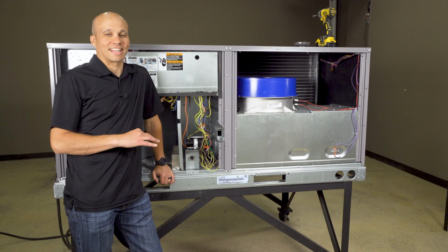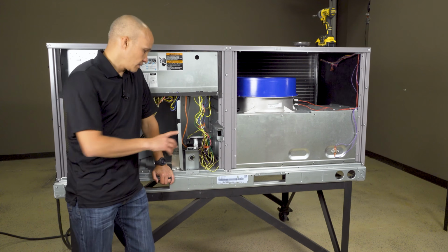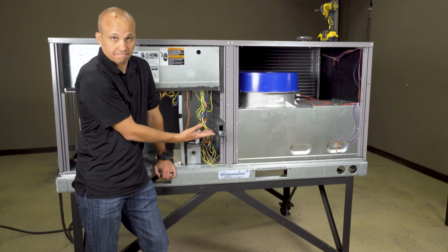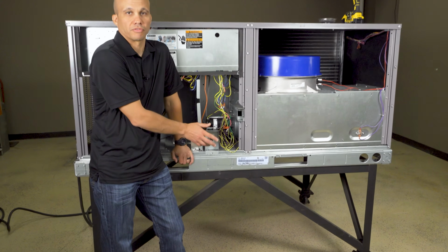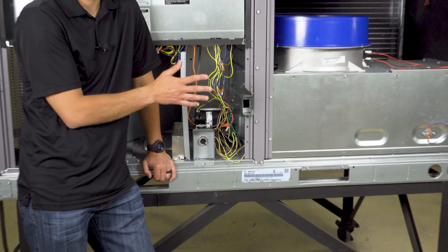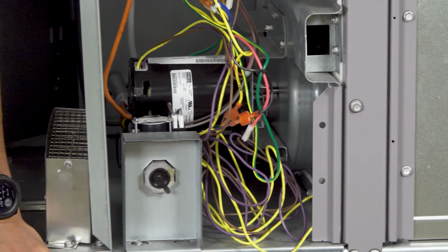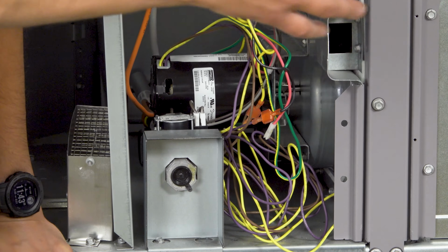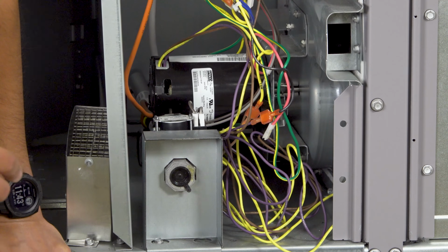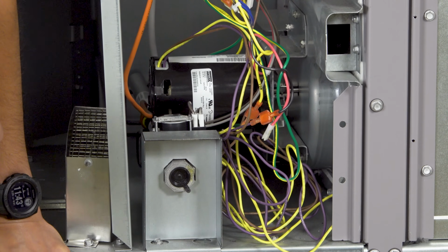Let's look at some of the components on a gas-fired rooftop unit. So for starters, we have a gas valve, obviously, because we have to have something that controls the flow. It'll either be an on-off valve, meaning one stage, or it might be a two-stage gas valve, which means I can turn on part way and then turn on all the way. And then on really complex systems, you might have a modulating one. But for rooftops, it's typically one or two stages.